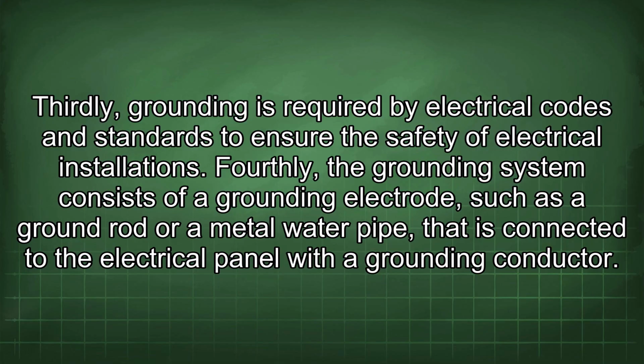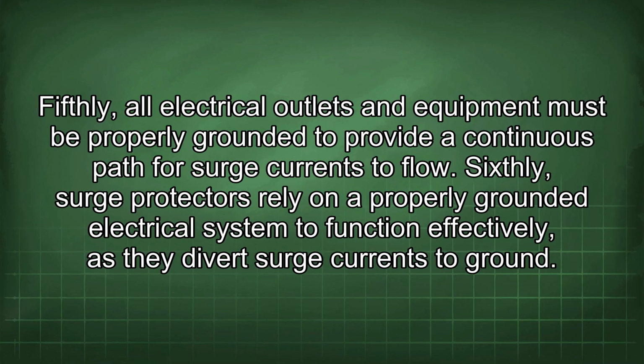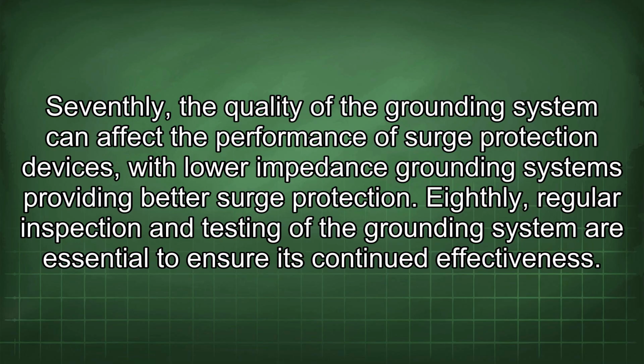Fourthly, the grounding system consists of a grounding electrode, such as a ground rod or a metal water pipe, that is connected to the electrical panel with a grounding conductor. Fifthly, all electrical outlets and equipment must be properly grounded to provide a continuous path for surge currents to flow. Sixthly, surge protectors rely on a properly grounded electrical system to function effectively, as they divert surge currents to ground. Seventhly, the quality of the grounding system can affect the performance of surge protection devices, with lower impedance grounding systems providing better surge protection. Eighthly, regular inspection and testing of the grounding system are essential to ensure its continued effectiveness.